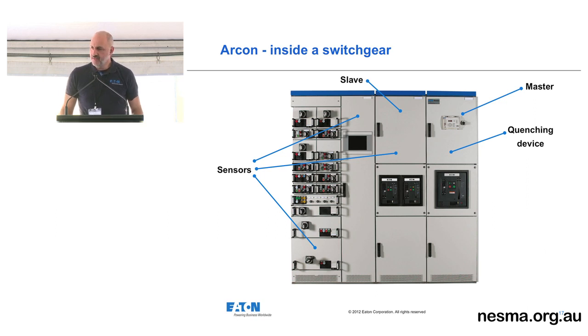What's also a clever trick that you can do with this is you can have a spare lead connected to one of the slaves. So if someone's working on the board and the doors are open, you can pin the optic fibre to your shirt. You can go around the switchboard with the doors open, so should an arc occur inside the actual breaker unit and you're front facing it, the flash on your shirt will detect the arc flash and will quench the system. This has been declared you can work on an open switchboard with minimum PPE because of the under 2 millisecond thing.